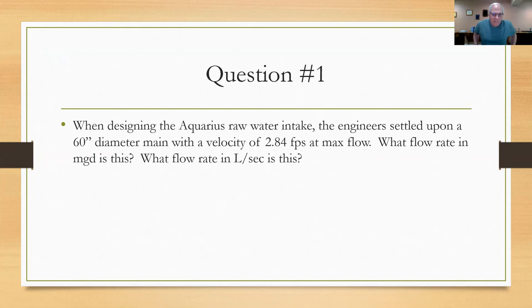So here's the first question that I'm going to ask. When they were designing the Aquarius raw water intake at this plant, the engineers settled upon a 60 inch diameter main, a five foot diameter main, with a velocity of 2.84 feet per second when the plant was at its max flow. So question is what flow rate must that be in MGD? When you figure that out then convert that to liters per second. So there's two answers they're looking for. They're going to use the Q equal AV formula. At least that's what I would use. So again, if you want to stop the video now and work the problem, go ahead and do that. I'm going to proceed to the answer now.